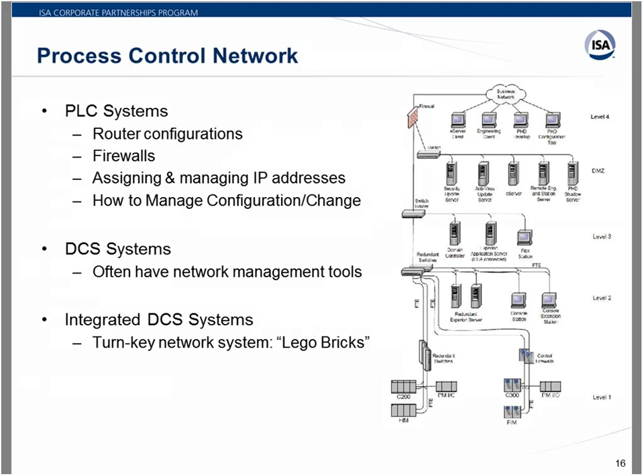So in between the PLCs or the controllers, you'll find your data servers. And this is what brings the data from the controllers or the PLCs up into the control system. So on the PLC side, typically a data server has to be configured for each of the PLCs. Often you'll have to create a separate tag database or I/O list that is programmed to talk to the PLC, as in opening up data channels. And if you have multiple types of PLCs or multiple locations, sometimes you have to do quite a bit of configuration to get it going.